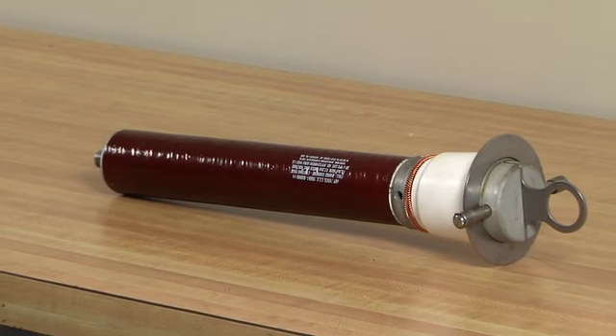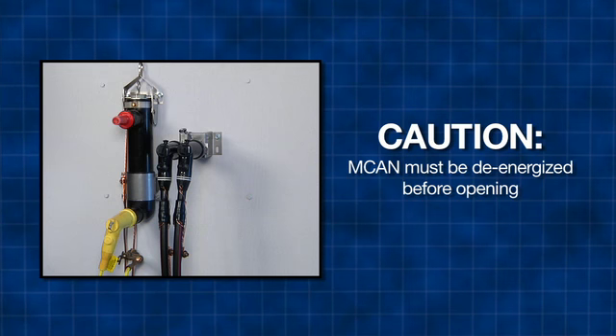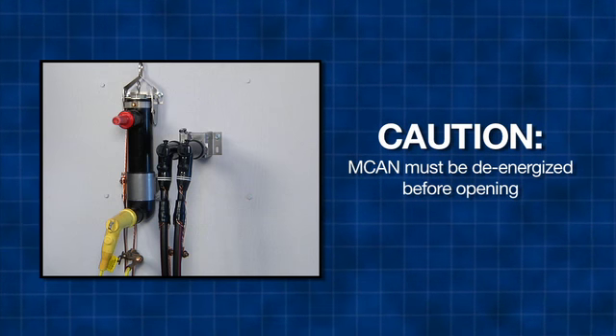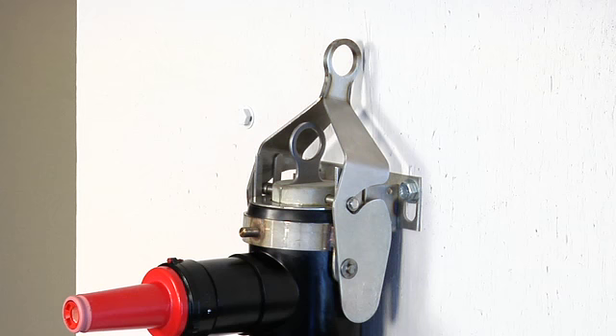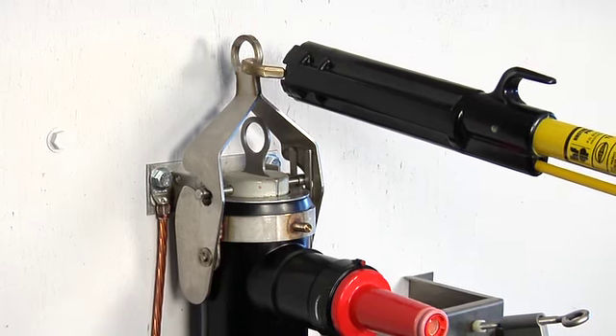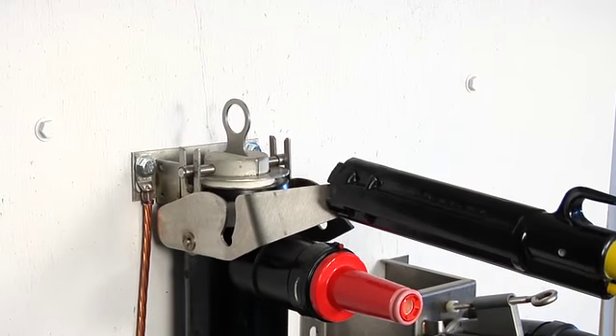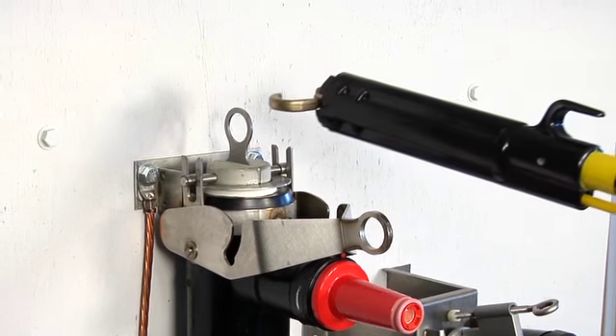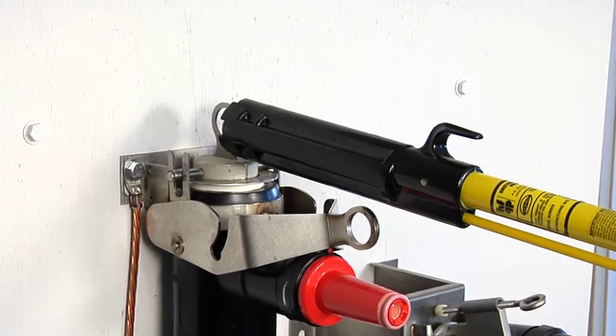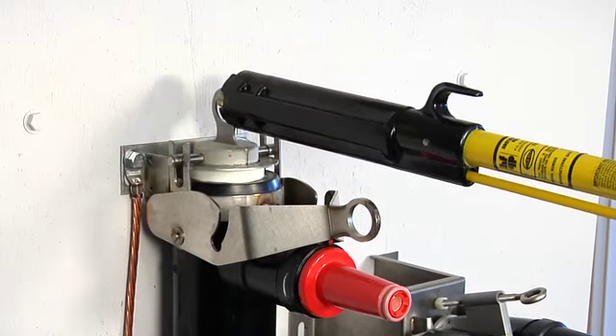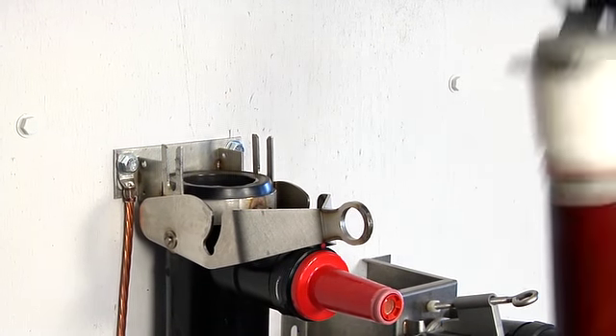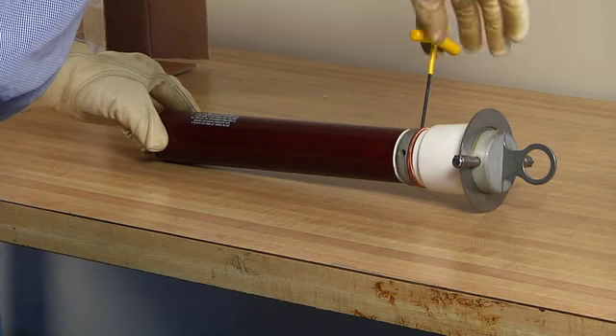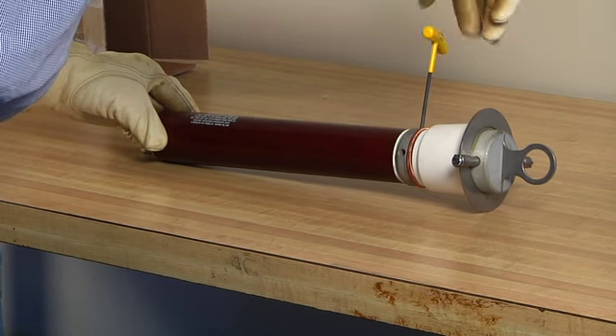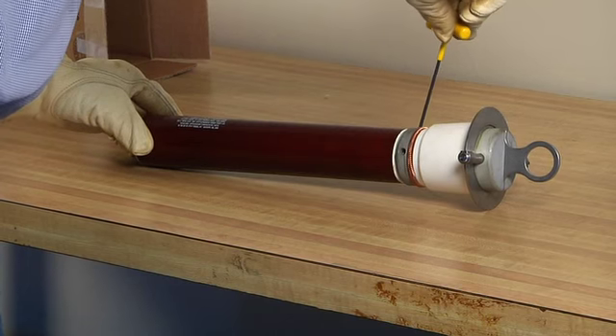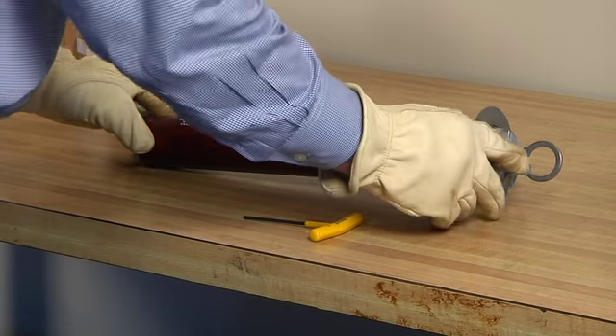Fuses are easy to replace as follows. It is very important to de-energize the circuit before opening the canister. To remove the fuse, first, pull the locking pin, if equipped, to release the canister lever. Next, lift the lever with the hook stick until the guide rod is free of the lever arm. Then, pull the fuse out with a hook stick. For a horizontal mount, a second hook stick may be required to support the end of the fuse as it first exits the canister. Loosen the 2 set screws with a 1/8 inch Allen wrench. Finally, separate the fuse from the end plug.